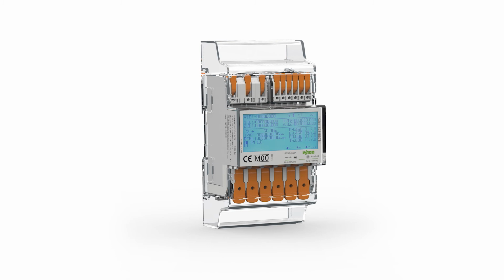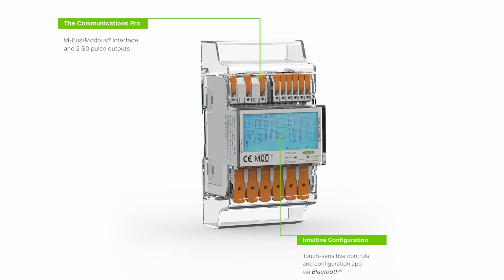Now I will show you the 5 key features of the new energy meters. I will start with the communication interfaces. We have an integrated Modbus and MBus interface, and additionally 2 S0 outputs integrated. These 3 interfaces are for all 3 types. So this was the communication. The next one is the configuration. We can configure the new energy meter generation with touch sensitive elements, or we can configure it with the Bluetooth configuration app.